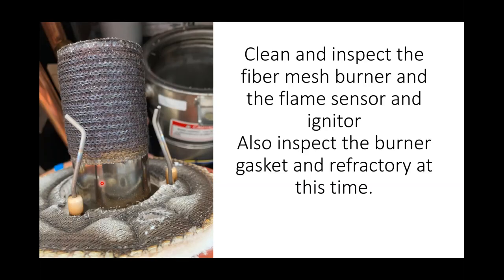Next thing you're going to want to do is clean and inspect the fiber mesh burner. We'll blow this off with some compressed air, vacuum it off. We do not want to clean the mesh off. We want to leave the mesh there, but vacuum it down. Make sure that the refractory is still intact.